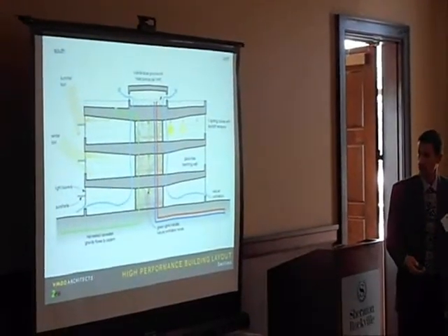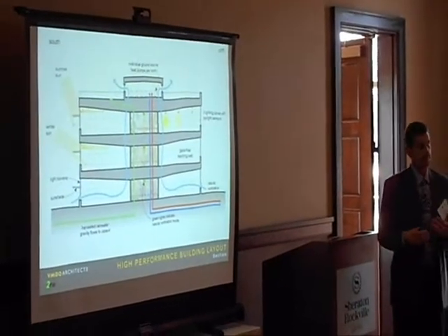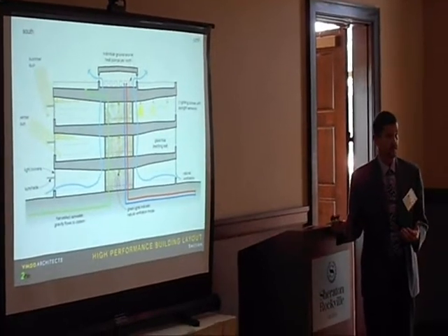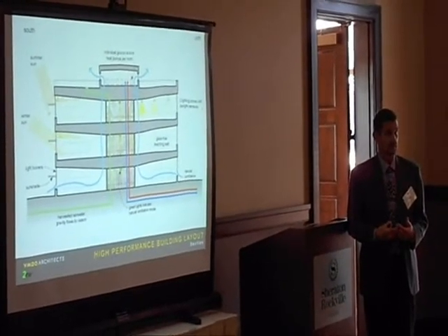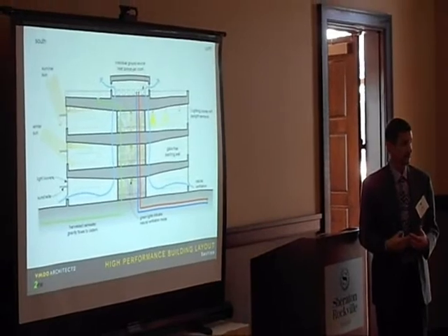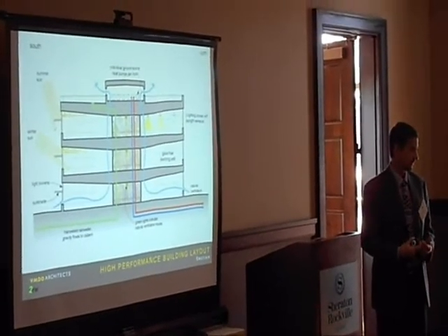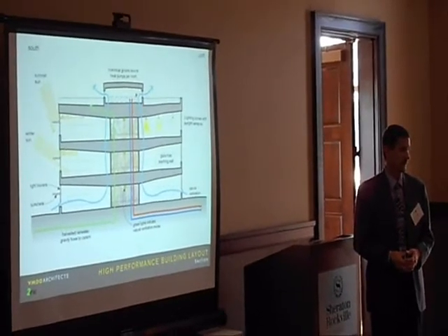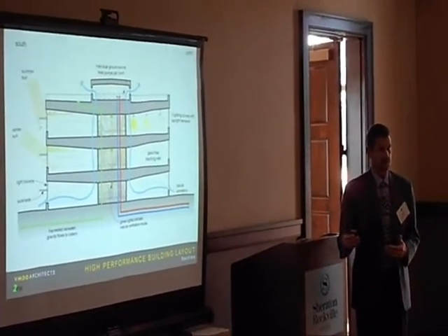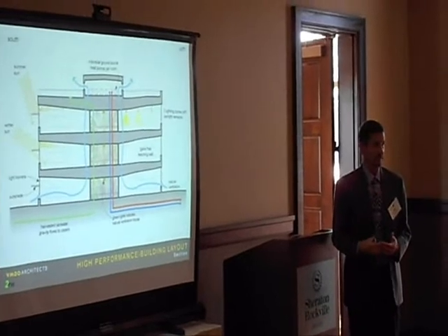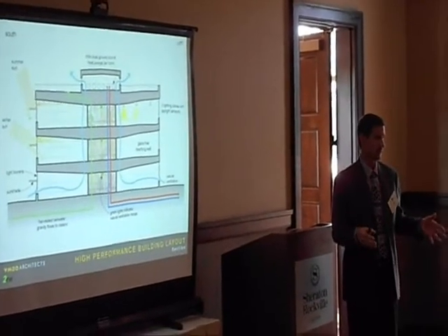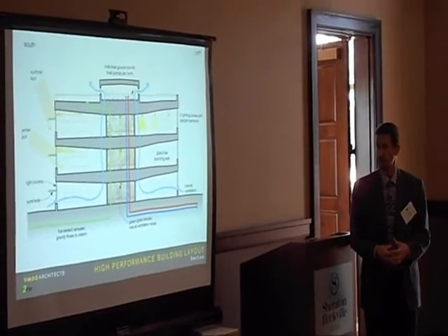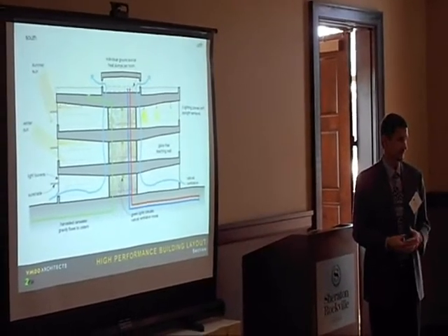So, I guess to quickly go over the systems that we have here. Again, this building was sort of the culmination of 5 projects. And the first project that we started had a water source heat pump system. It was the best life cycle cost that we identified at the time. And 3 of the schools, or 3 of the projects from that point had water source technology in them. A couple of them were 4-pipe. But they really liked the water source type systems.